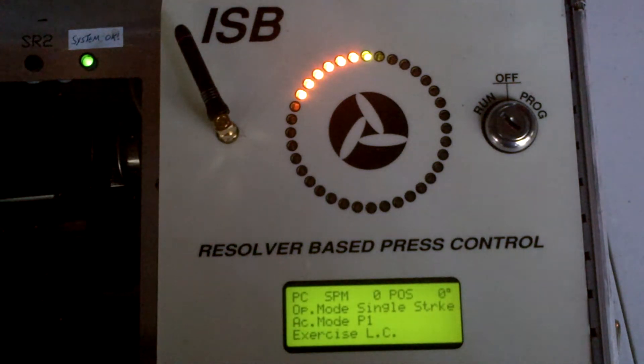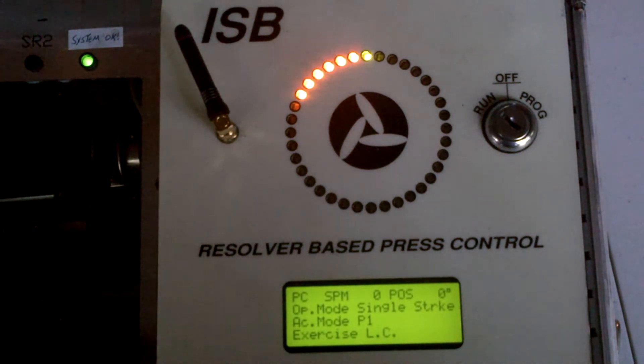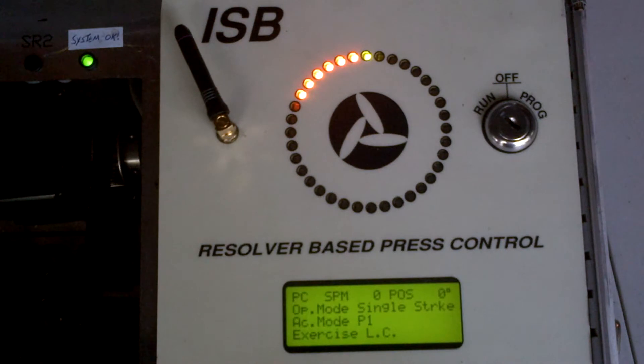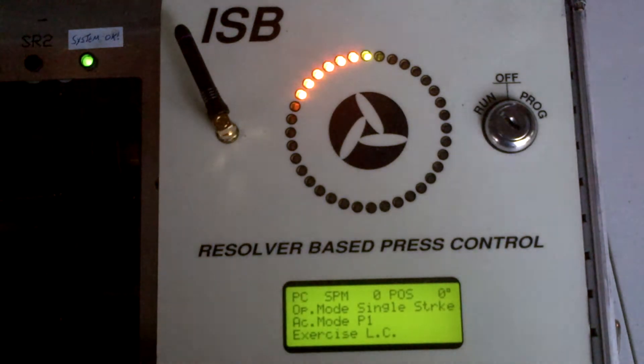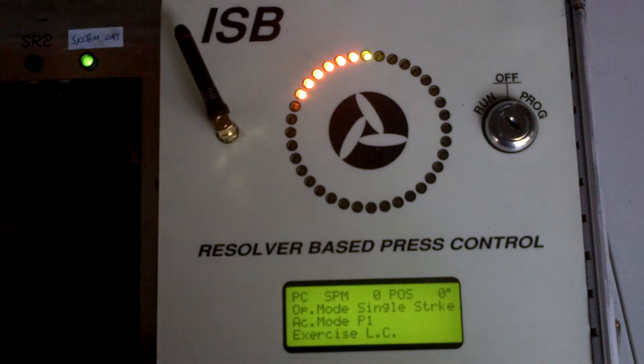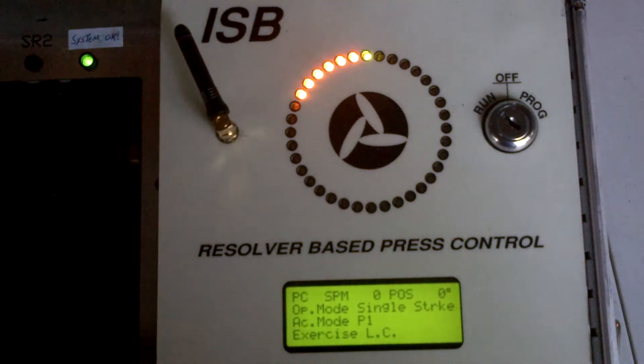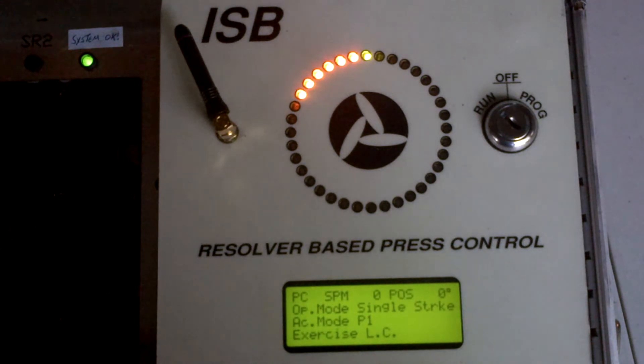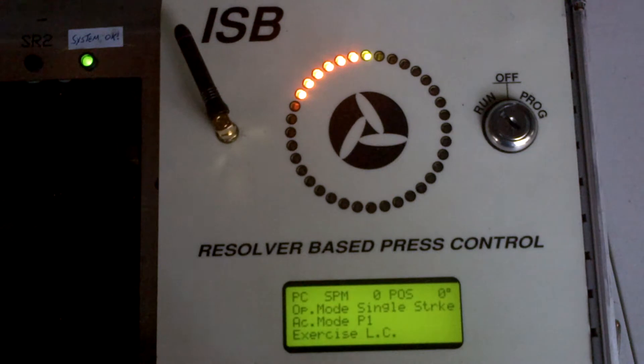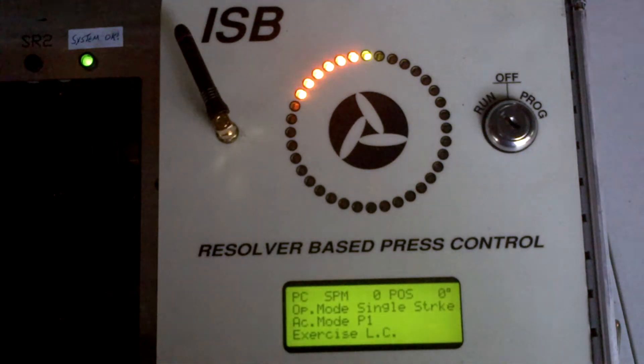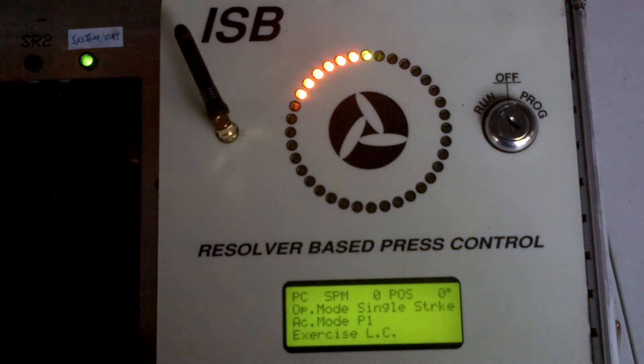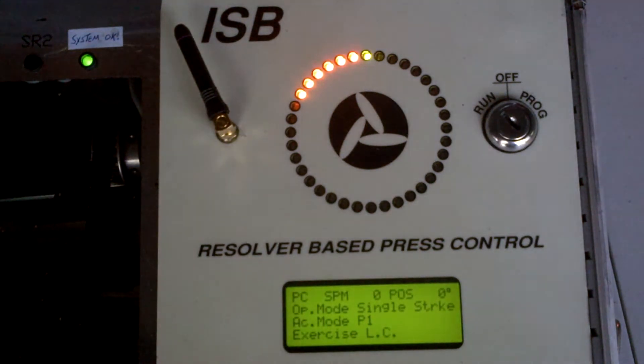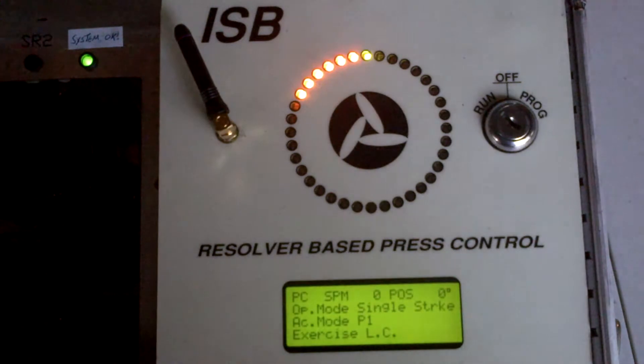you will need to do a resolver offset and check your direction of the resolver. So today I'm going to show you what you would do once you have installed the RBPC, wired all the necessary inputs including light curtains and interlock gates, connected the resolver to it, mounted the proximity switch sync cam on the crankshaft extension, and have the cam set to come on at exactly top dead center, zero degrees.